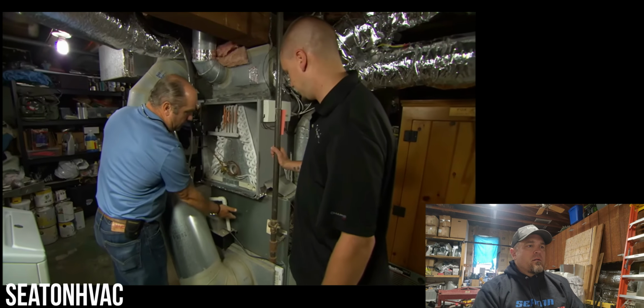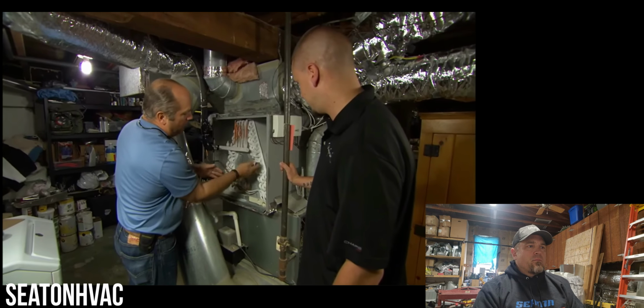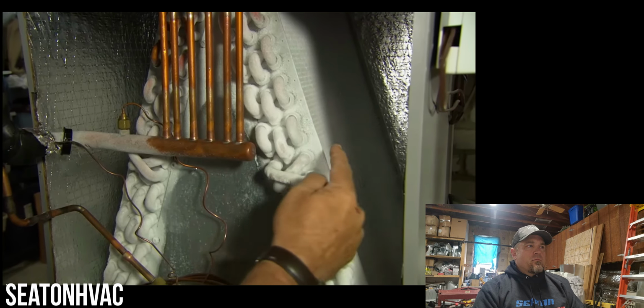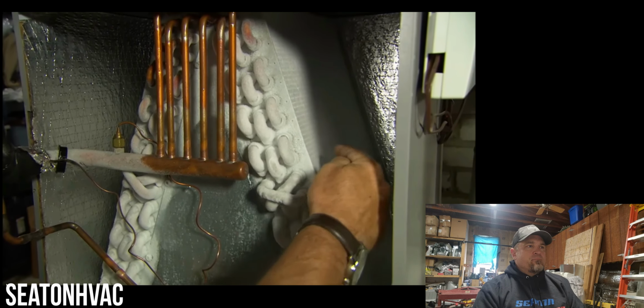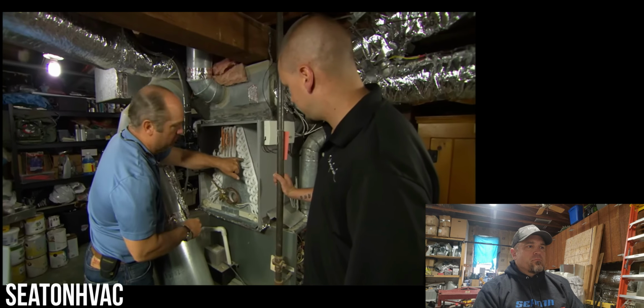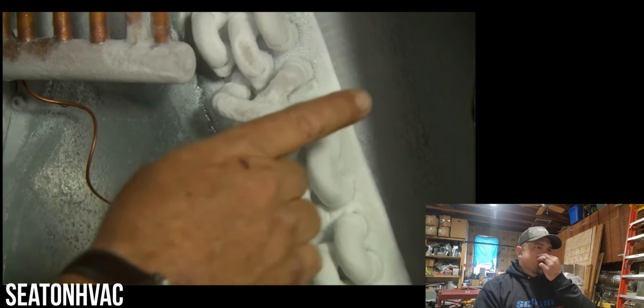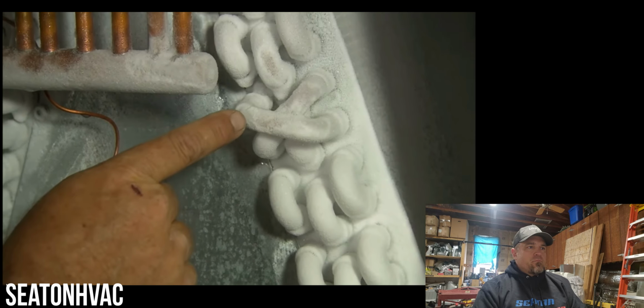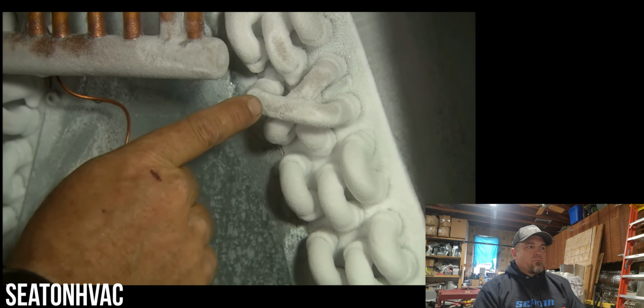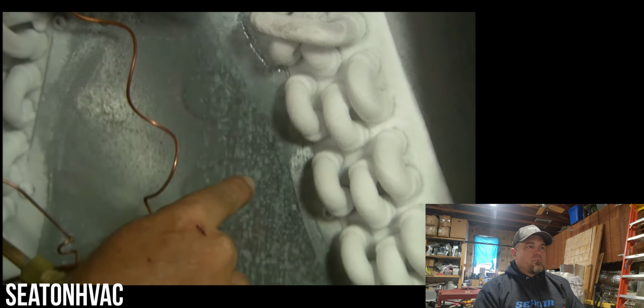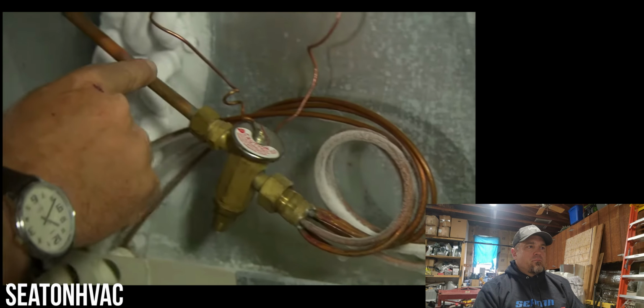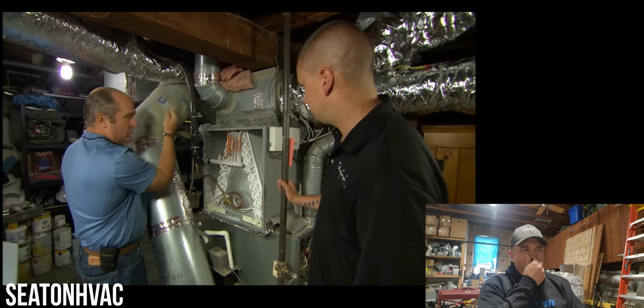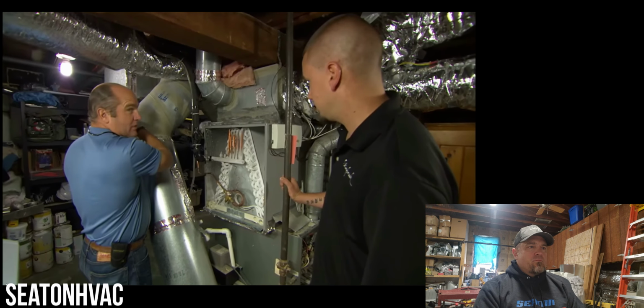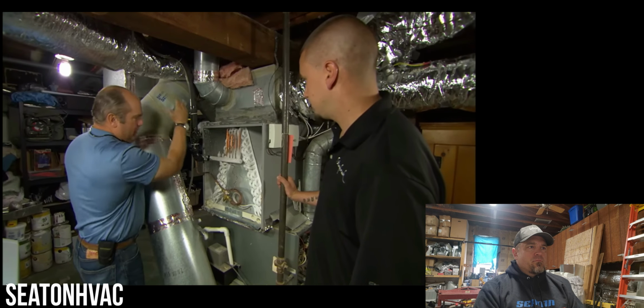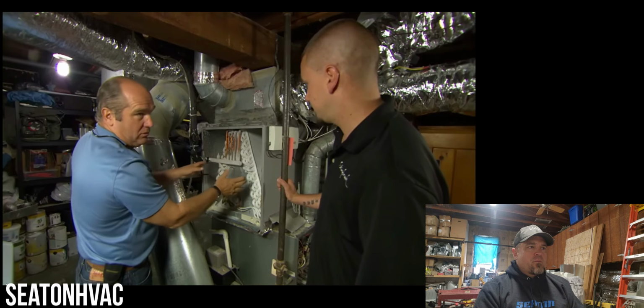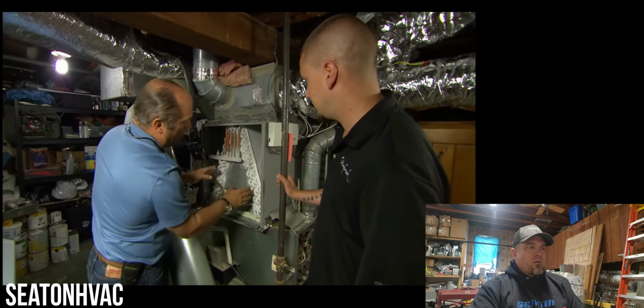So air is blown across and through this coil. You can see the coils right here, and there's also fins in here that the air blows across. The coils are filled with refrigerant. So when the warm air goes across, any heat that's in the air gets absorbed in the refrigerant inside of these coils, and it gets transferred through this line right here to outside. It goes through the compressor outside and through the outdoor condenser, and now it comes back really cold right here. In your case, it's way too cold. And now it's freezing this whole coil.